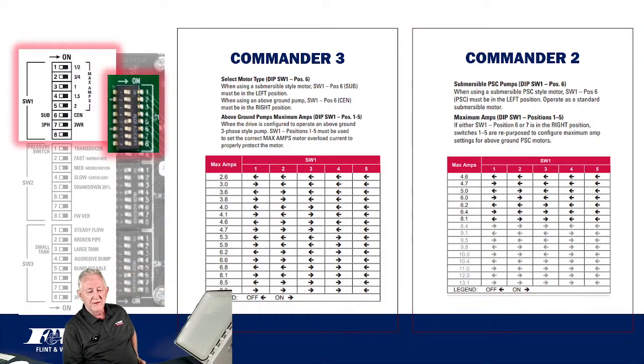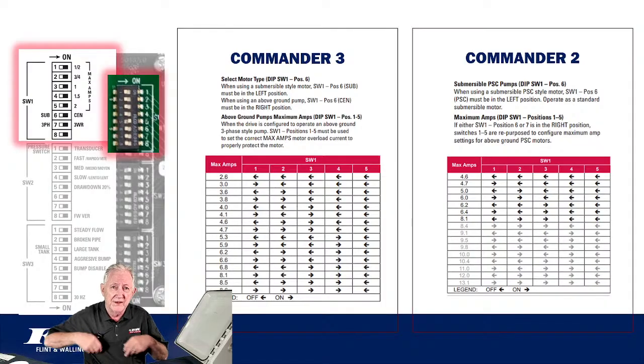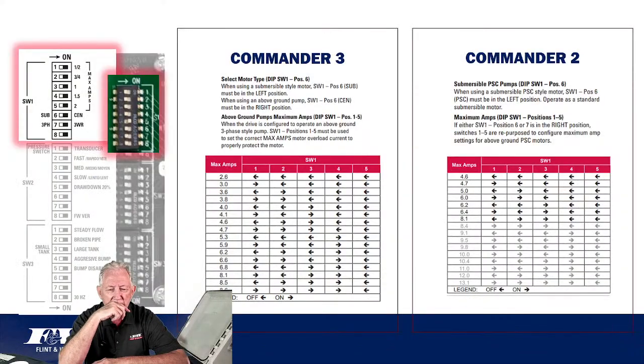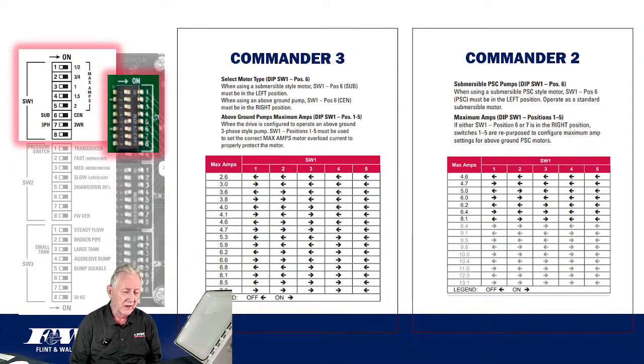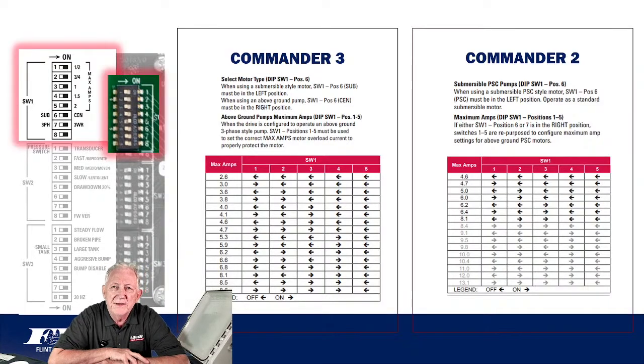Again, these pump companies don't manufacture their own motors, and they're using somebody's. So one of the ways that we're going to determine and let this drive know what type of centrifugal motor it's operating is we're going to go to this chart that will indicate where we're going to select for max motor amps. Now, that label on the inside cover that we talked about early on, we don't need to go back to that, but one thing I want to bring up is it's got a QR code on it. I should have mentioned it then. If you scan that with your phone, you're going to come right to the instruction manual, and here's where we're going to find some of these charts. So, for instance, if you look at that Commander 3 chart there, come down to, what, 6.2 max amps.